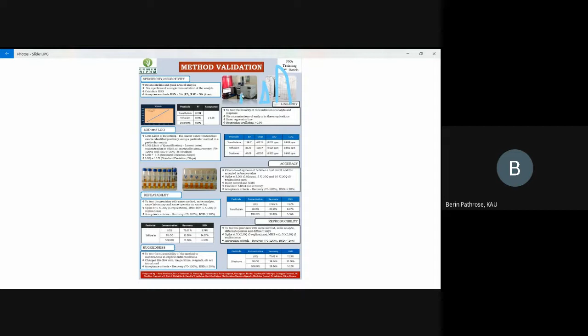Yes, sir. Okay. So if you are injecting a single concentration 6 times, the instrument should show about a uniform quantity. If you are injecting 10 ppm, all 6 times it should show somewhere around 10 ppm. It should not show 5 ppm one time, 6 ppm another time, and 13 ppm another time. So there we use the peak area, and we calculate the standard deviation for peak area also.